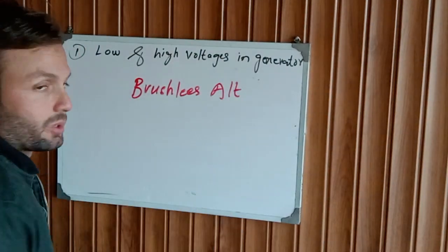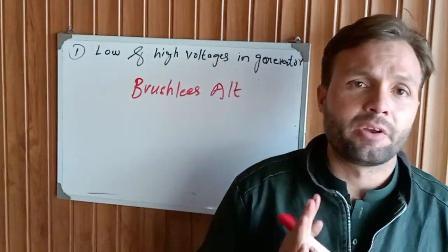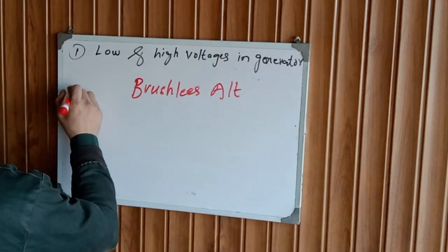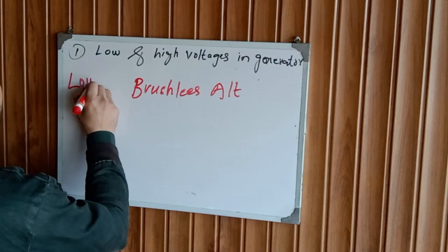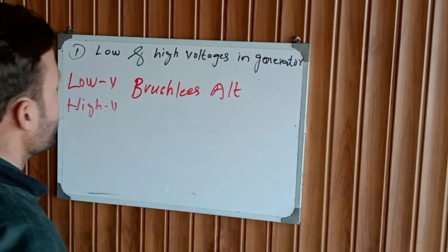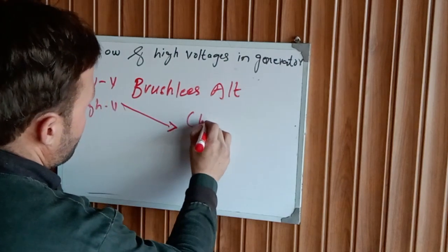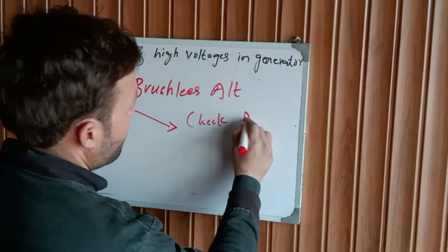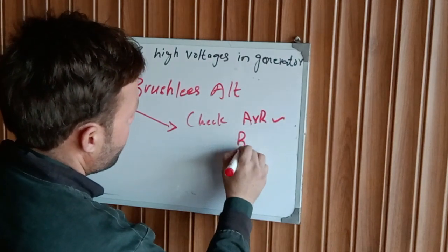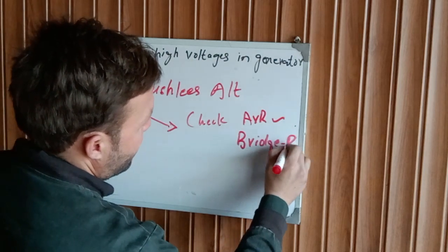The brushless alternator has an AVR, is simple, has low maintenance cost, and is very reliable and very powerful. For the brushless alternator, low voltage or high voltage: check the AVR and the bridge rectifier.